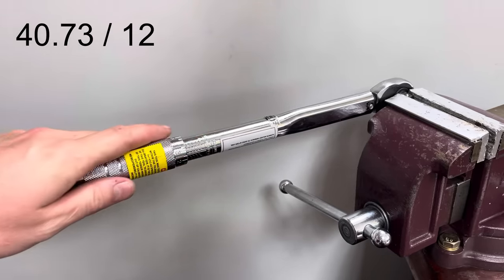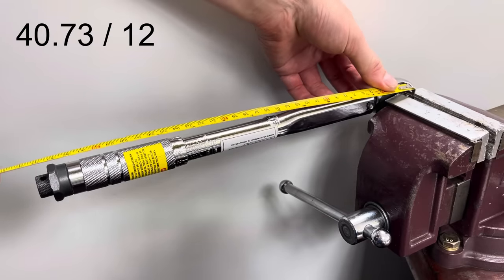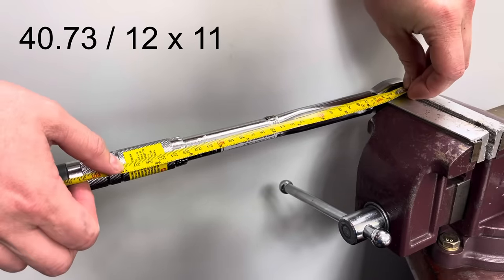So, we take that weight, we divide it by 12, and then we need to decide on, again, the lever length, how long we're going to go from the middle of the square drive to about the middle of the handle. In this case, let's have a quick look, we are 11 inches.